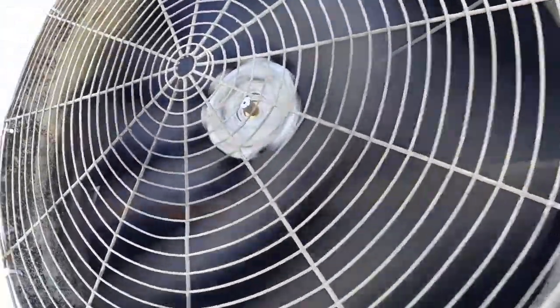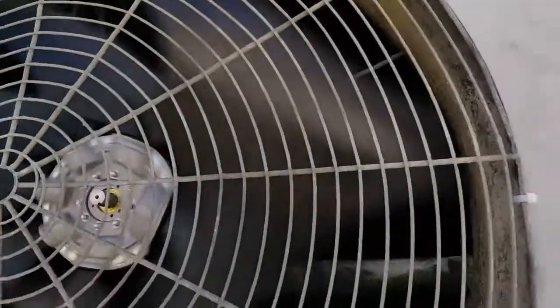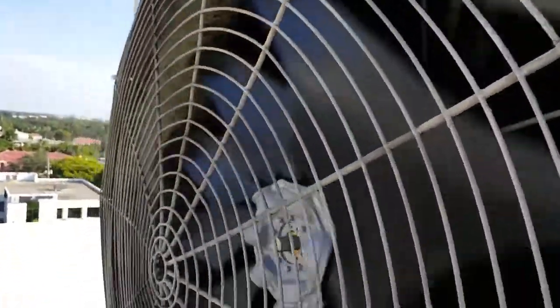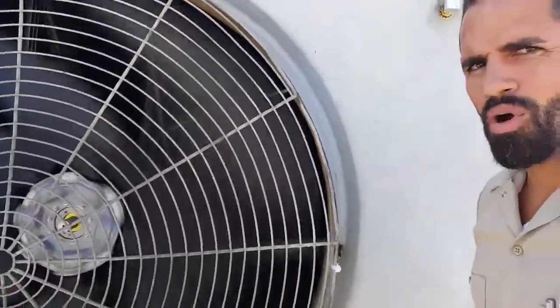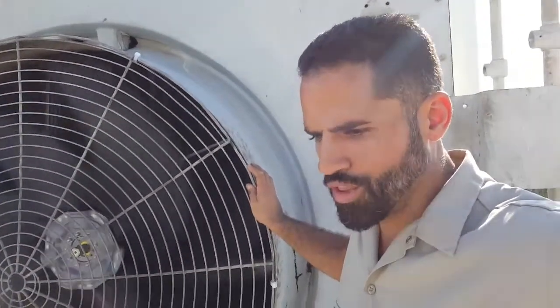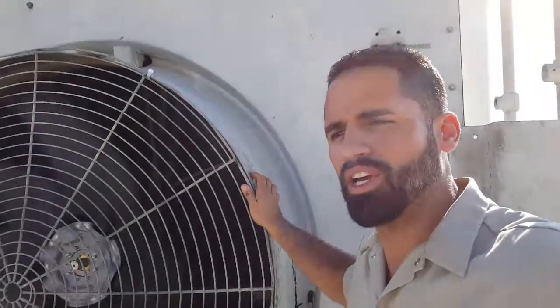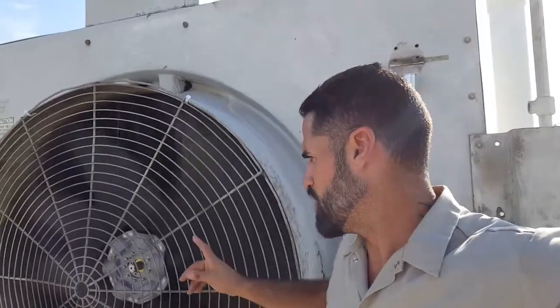Okay everyone, we're pretty much wrapped up. Finally we got our other piece for the oil fill — this oil fill is for the gear reducer. Again, this was a Pro-Tech cooling tower, which they didn't have any parts for here in South Florida. We actually had to order the fill from India, but after doing some research and getting some measurements, we were able to come up with a Marley fill that was pretty much a carbon copy, and we changed out the fill.